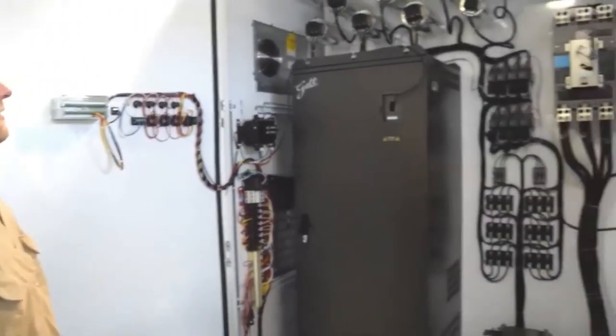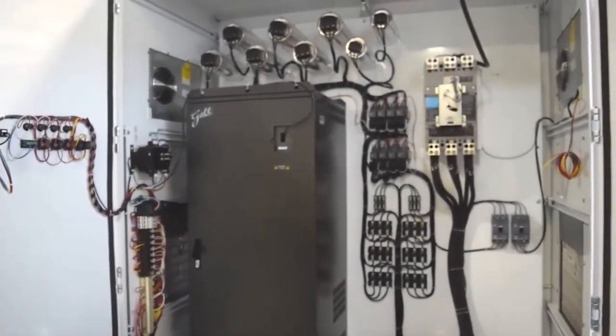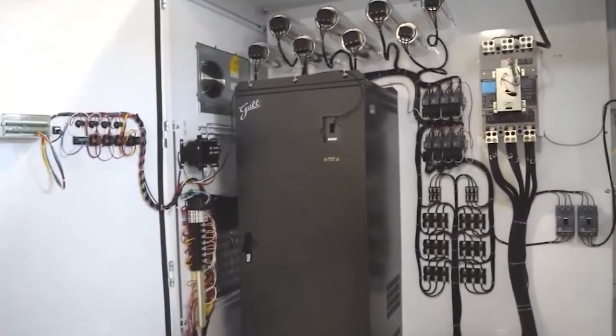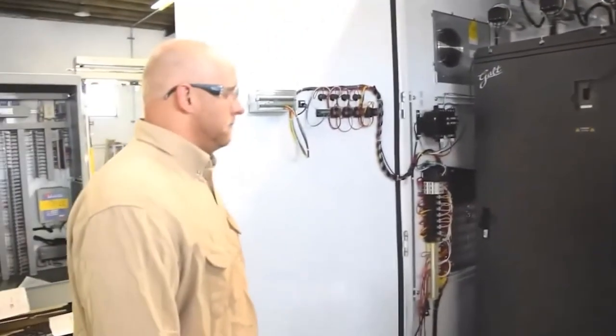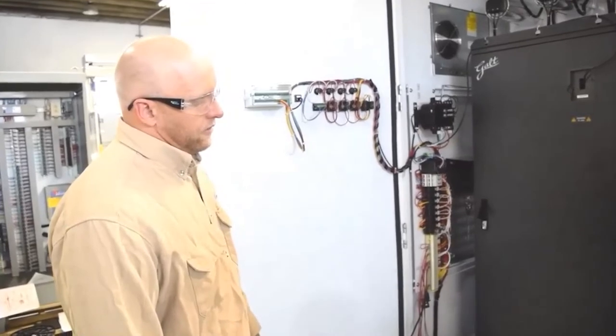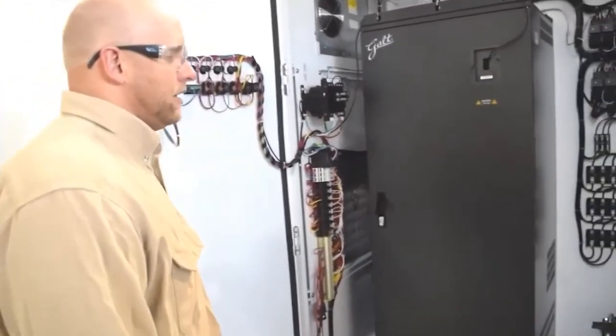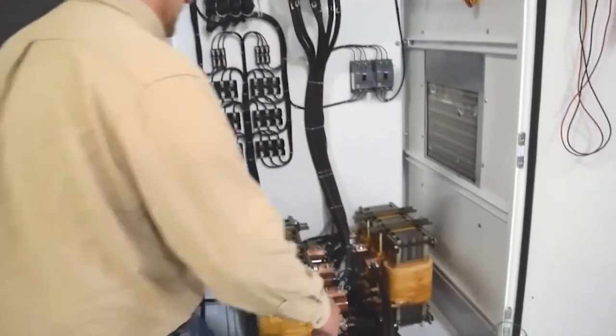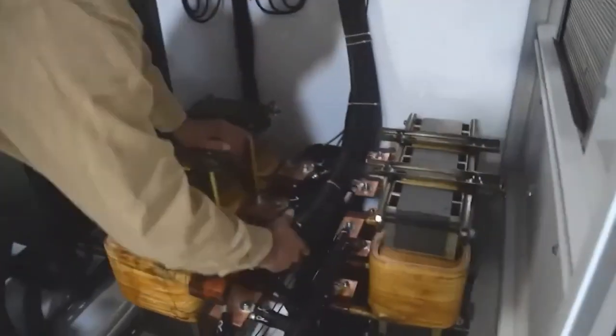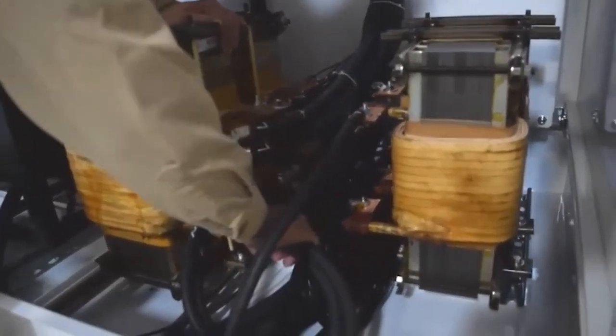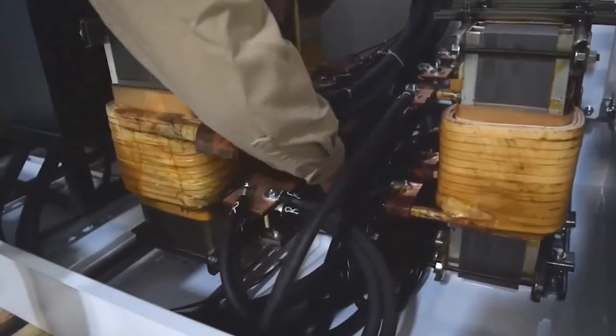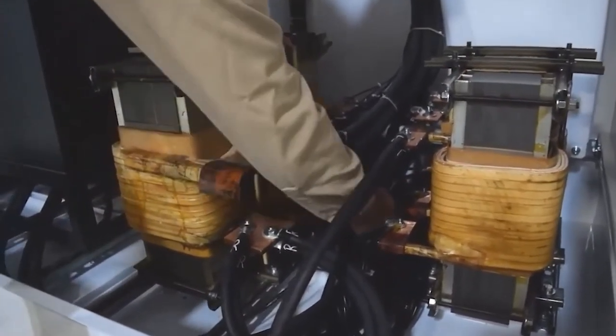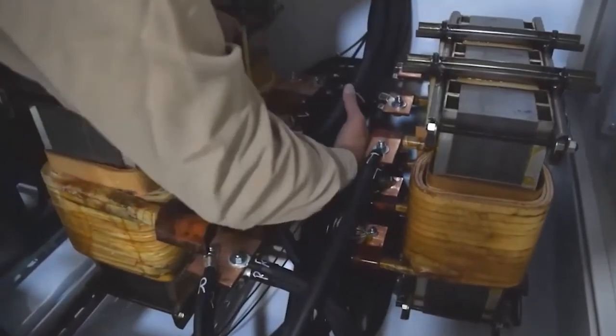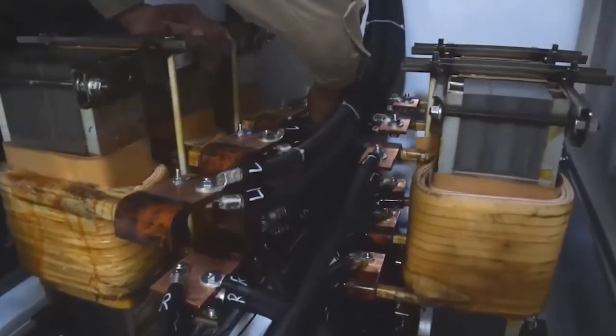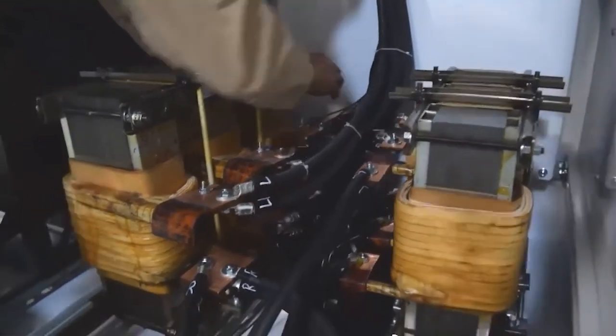So now that we've verified everything's off, we'll give you an overview of what's in the cabinet. The first thing that we're going to do when we get inside the cabinet is just stand back and do a visual inspection. We're looking for all kinds of things inside the cabinet. We're looking for things that are burned up. We're looking for debris in the cabinet. We're looking for maybe insects have gotten inside of it, maybe a rodent. We've seen all kinds of crazy things get inside these cabinets. The first thing we do is verify we don't have anything in the cabinet. Then I proceed to go through and make sure everything's tight.